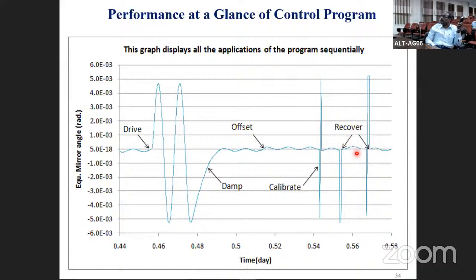And these are two things where you're showing that by chance something goes wrong in your program or things like that, the compensating plate may get driven beyond its limit, and you should not lose the signal. In that case, the supply for the encoder motor is provided through a limit switch. The moment it goes beyond this limit range of the optical lever, the switch opens, and the program finds out initially itself where it was and parks back this compensating plate there. Same thing happens in either direction. So this is very important, because once you lose the signal, it's very difficult to get back. So this is the safety precaution which has been inbuilt into the system.